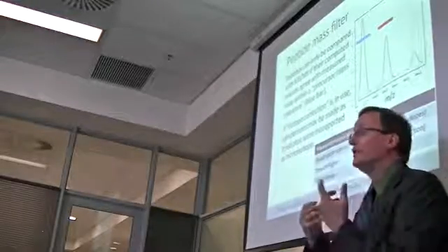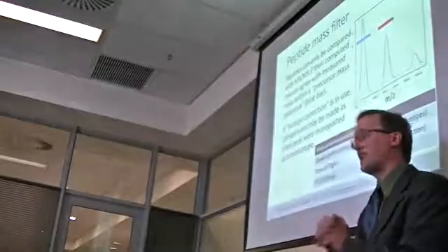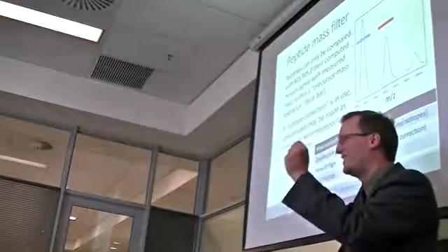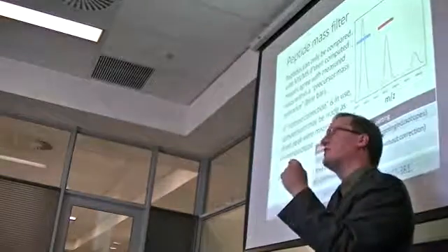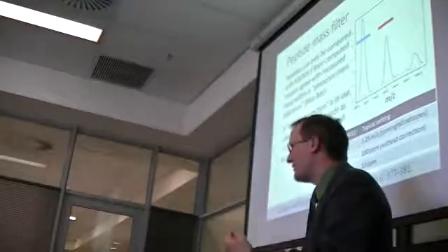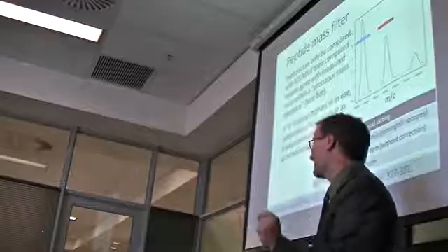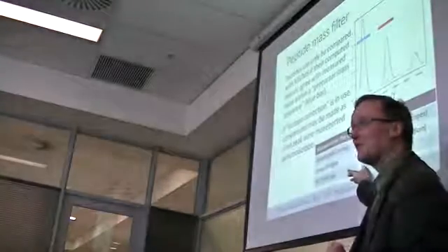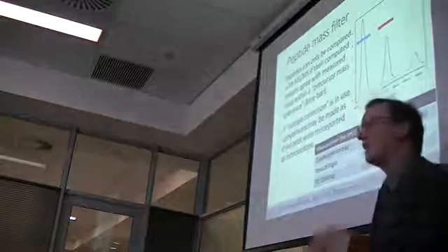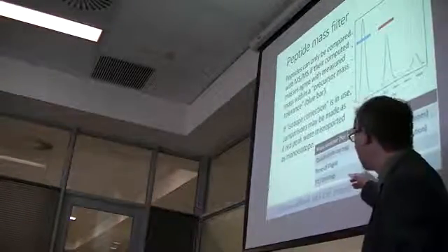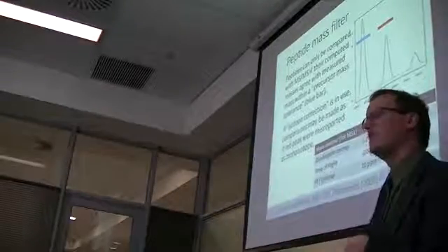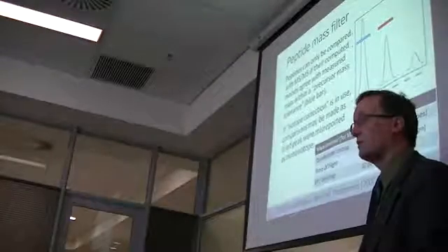A really, really good time of flight can give you 10 ppm mass accuracy, meaning that you know the mass of an ion is within 10 parts per million. If you think about that, if you divide something that has a mass of about 1,000 by 1,000,000 and multiply that by 10, that's how accurately you know it. That's astonishing. Generally speaking, when I'm searching time of flight data, I usually assume a wider mass accuracy than that and allow for up to 100 ppm mass error. If I'm measuring something from one of these Fourier transform instruments that I mentioned, I usually assume that it has, say, a 10 or 20 ppm mass accuracy.